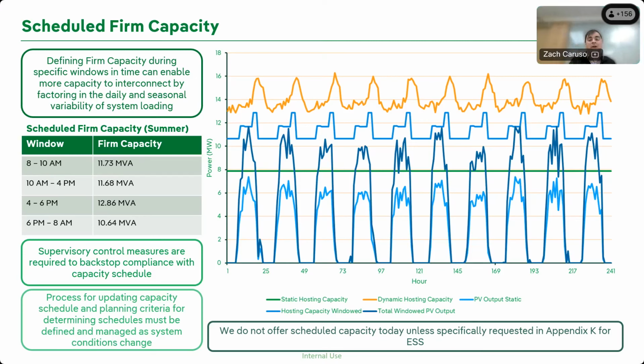We don't get all the way to that dynamic line because we have to build in these margins, since we're not actively feeding back the real-time dynamic hosting capacity, and we're still relying on the study to drive what these operating envelopes are, or rather these limited generation profiles, as we see out in California. It has advantages, but it also introduces challenges, because now we have to manage those schedules and keep track of them. If one site comes on with one schedule and another site comes on with a different schedule, we have to proactively take each of those schedules in and include them in the next study, and so on down the line. And then you get into concepts like storage, where resources are very dispatchable.